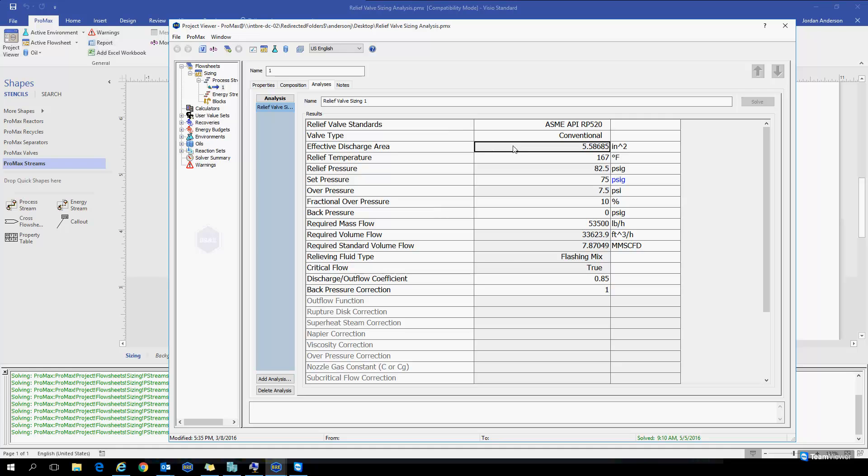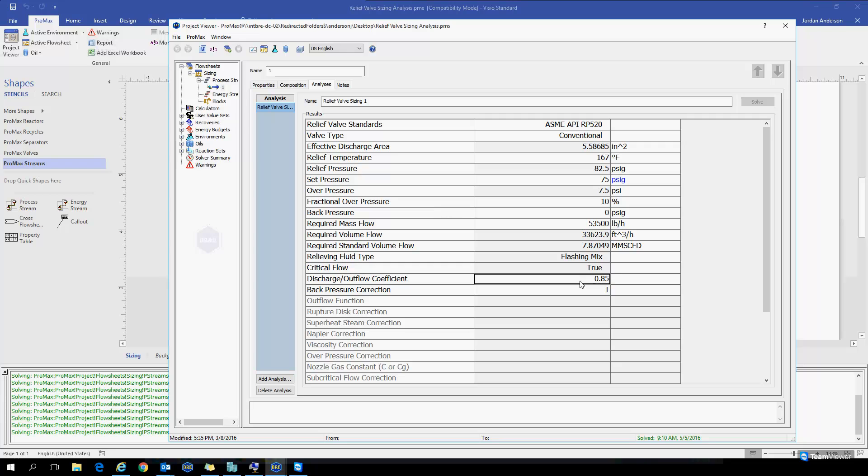Promax is going to calculate for us an effective discharge area, which is the area that our valve will require according to the discharge coefficient we have input here down below. You'll see Promax has filled this in with a default value. But if you knew your discharge coefficient, you could override this value, and Promax would calculate a different area according to that discharge coefficient.